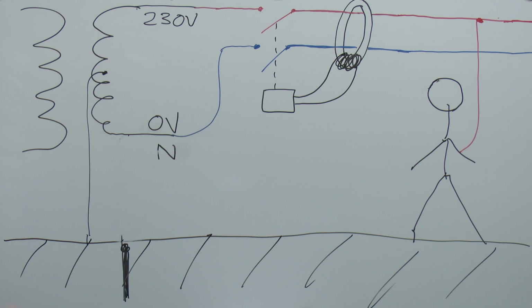In that particular situation you would generally have say 115 on each relative to earth, and again the RCD would then trip properly. So if you do have a generator which has this kind of setup, it's absolutely vital that the connection there is actually put into the ground using an earth rod or earth stake of some kind. Otherwise the RCD that's usually included in these devices won't actually do anything in the event of a fault, and if you're powering several pieces of equipment, that could easily lead to a very dangerous situation.